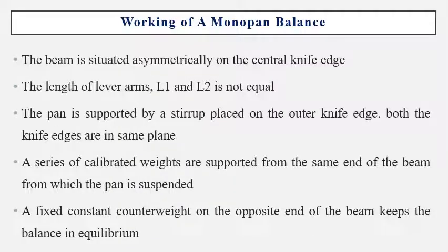Working of the mono-pan balance: the beam is placed asymmetrically on the central knife edge. The length of lever arms L1 and L2 are not equal — that is why both arms are asymmetrical, not symmetrical. The pan is supported by stirrups placed on the outer knife edge, so both knife edges are on the same plane. A series of calibrated weights are supported from the same end of the beam from which the pan is suspended.